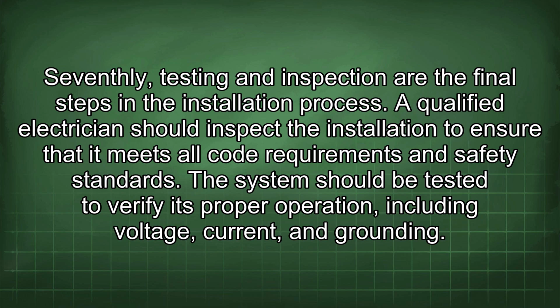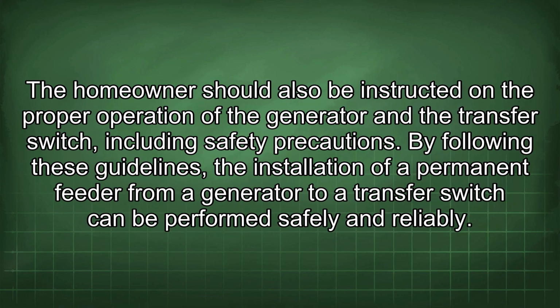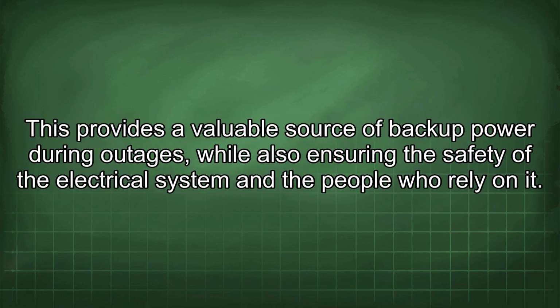The system should be tested to verify its proper operation, including voltage, current, and grounding. The homeowner should also be instructed on the proper operation of the generator and the transfer switch, including safety precautions. By following these guidelines, the installation of a permanent feeder from a generator to a transfer switch can be performed safely and reliably. This provides a valuable source of backup power during outages, while also ensuring the safety of the electrical system and the people who rely on it.